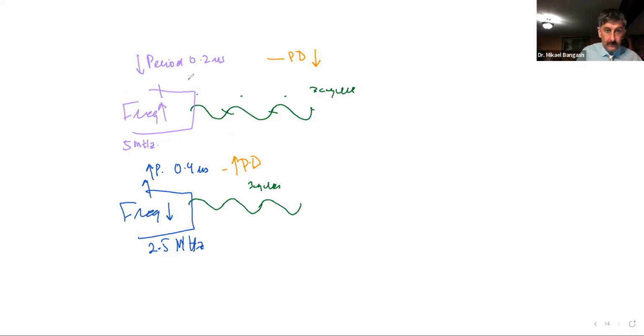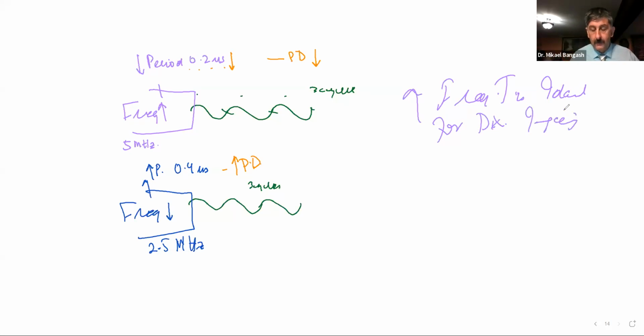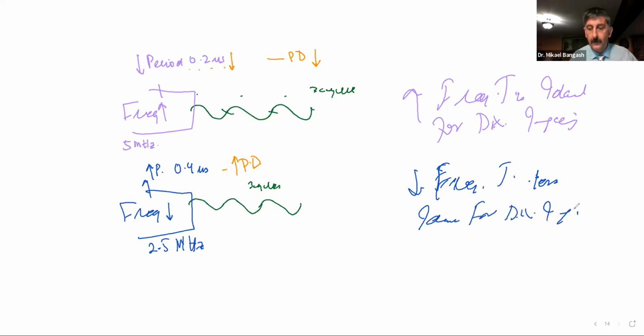Mainly, because in both cases we had the same number of cycles, it's directly due to the lower period and greater period, which is inversely related to frequency. So what we mainly can say is that high frequency transducers, this one here, are ideal for diagnostic imaging, whereas low frequency transducers are less ideal for diagnostic imaging.